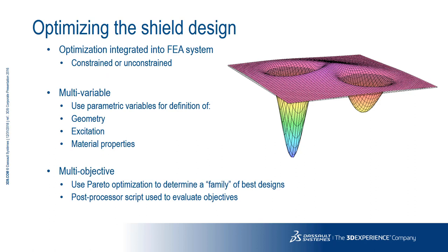The issue of MRI shielding is a class of mathematical problems suitable for an automated optimization technique. Since Opera contains an integrated optimizer module, we'll look at how to produce an optimal shield design rather than an efficient over-engineered example. Opera's optimizer can solve constrained or unconstrained problems. The variables to be used are specified during the definition of the model — we can specify variable dimensions within the geometry, variable parameters such as plate thickness, variable material properties, or the problem excitation can be defined as a parameter.